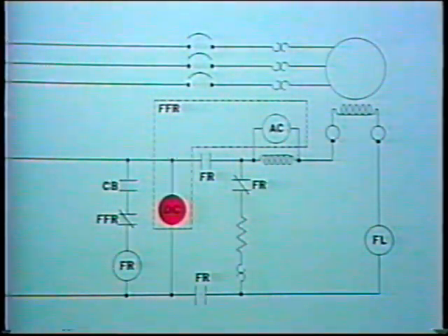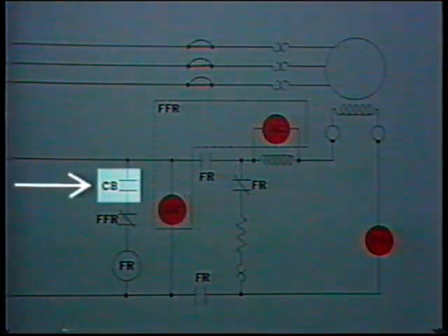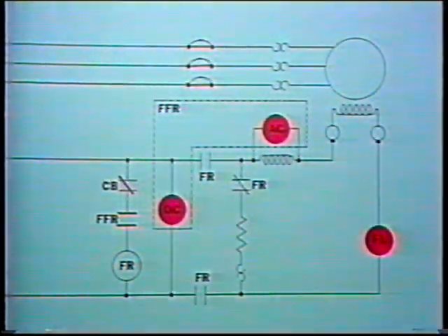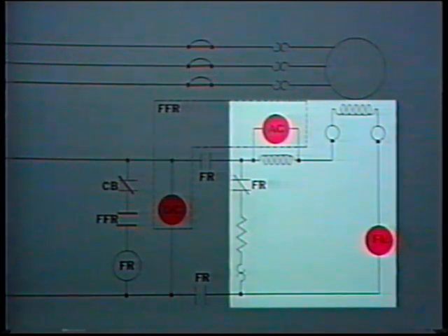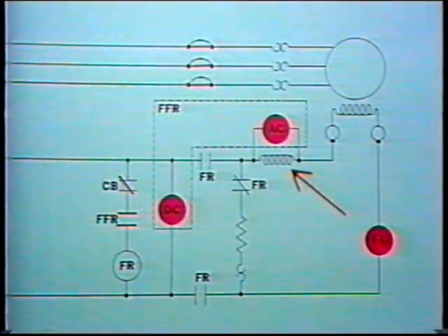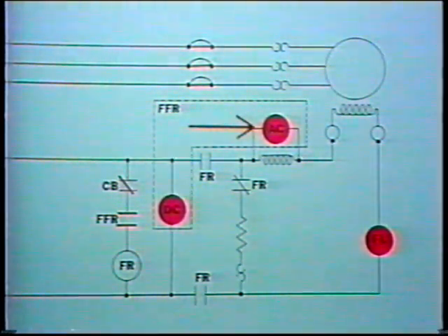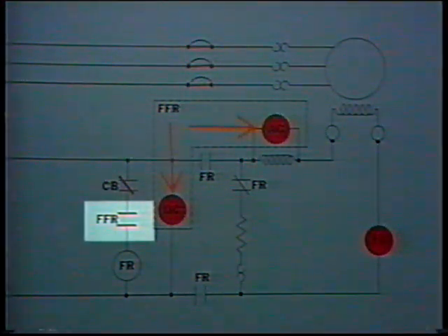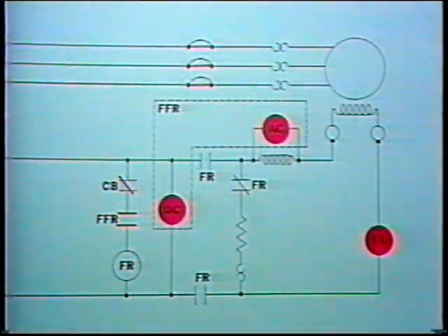Let's take a look at how the field frequency relay operates. As we said, when the circuit breaker is closed at motor start, these contacts in the rotor circuit close. At the same time, the field frequency relay contacts open. The reason that they open is that the stator field induces an alternating current in this part of the circuit. When alternating current flows through an inductor, there's a voltage drop across the inductor. The voltage drop across the inductor that's in parallel with the AC coil causes current to flow through the AC coil. The AC coil aids the already energized DC coil in opening the contacts of the field frequency relay. In a moment, we'll discuss why there's a voltage drop across the inductor. But for right now, let's take a look at 2 other components in the circuit.